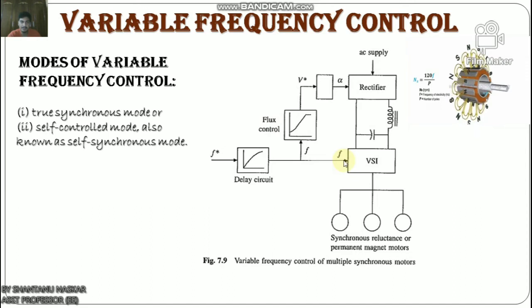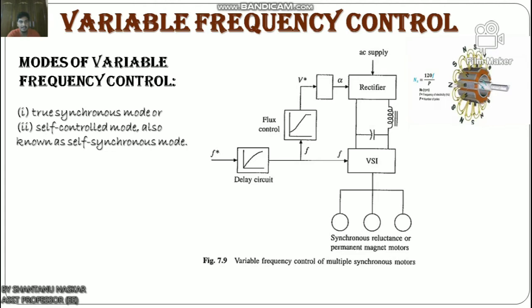Plugging is not used for synchronous motors as high plugging current can cause disturbance and damage. Now we will discuss the control methods. The first is variable frequency control. A drive operating in true variable frequency control of multiple synchronous motors is shown where frequency command f* is applied to a voltage source inverter through a delay circuit so that rotor speed is able to track the change in frequency. A flux control block changes the stator voltage with frequency to maintain constant flux below rated speed and constant terminal voltage above rated speed.